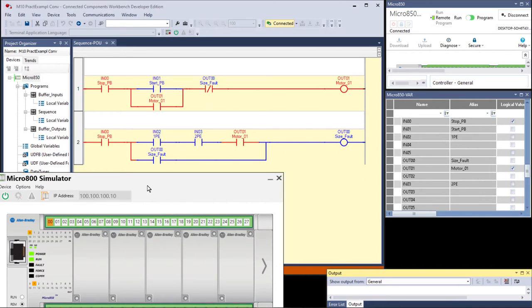Okay, we're running. Now let's do that again. Only this time, we're going to leave both of them blocked when we stop the conveyor, so the conveyor stopped. If the operator decides to reset it without removing the carton, double click on zero. Okay, it cleared, but watch what happens when you start it. It faults immediately. As a matter of fact, the conveyor is not going to move because you're talking about 300 milliseconds between when you press the stop button and when you release the stop button, because when you press the stop button, everything's false.